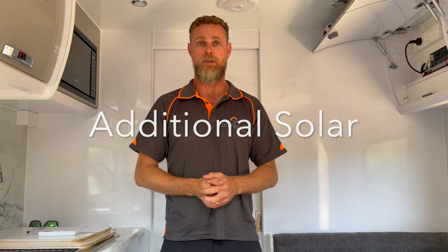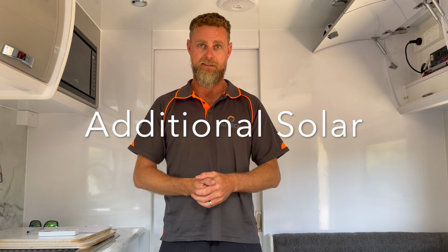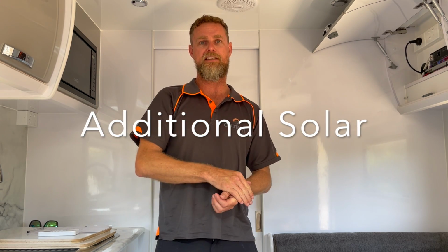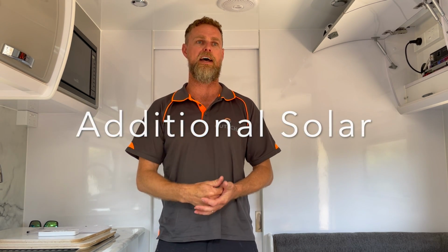Do you need to comply if you want to add additional solar to the roof of your caravan? Yes - the solar installation being done at the time will need to comply to AS 3000 Part 2 2022. Do you need to bring up to standard all the rest of the installation? No, you don't. However, it would be a good idea to do it at the same time for all the reasons we've talked about. So there's some good examples of when you need to comply and when you don't necessarily need to.